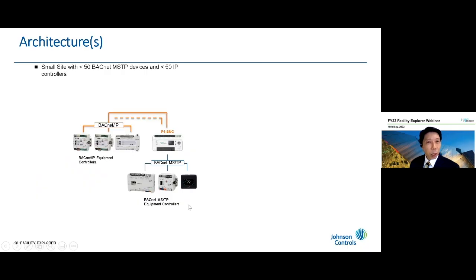Next one, well, you have some more IP controllers in the modern world in the building, so you can expand through the IP port. 50 devices on MSTP, then we allow a maximum total of 96 devices in the network, including IP and MSTP.